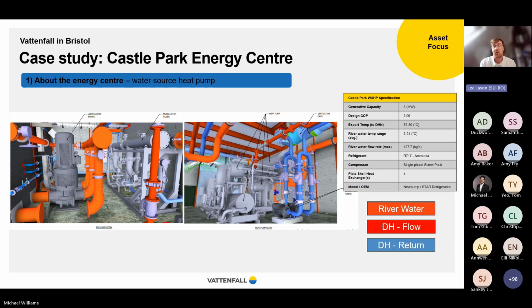We have a 2 millimeter mesh screening on our abstraction point with a backflush system in place, as well as a secondary self-cleaning mussel stop system, which essentially catches any sedimentary material and returns that back to that same body of water.